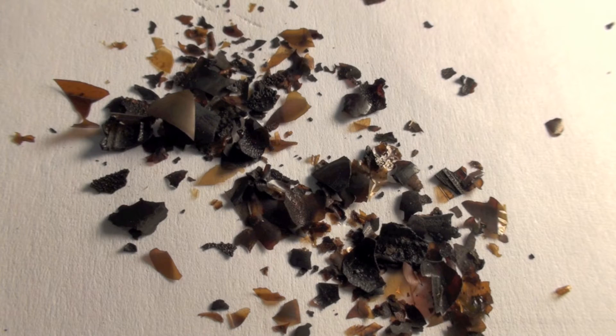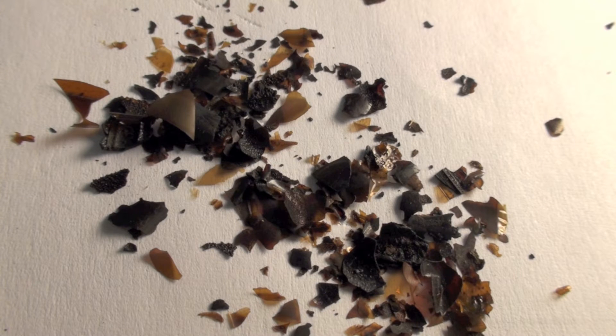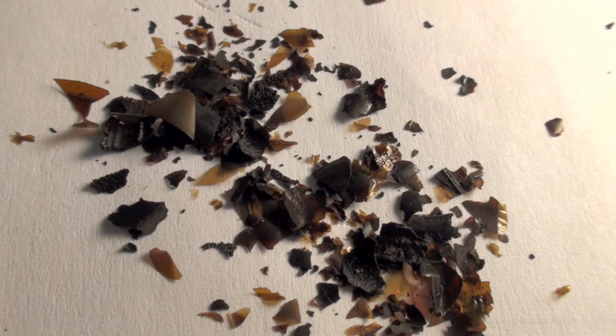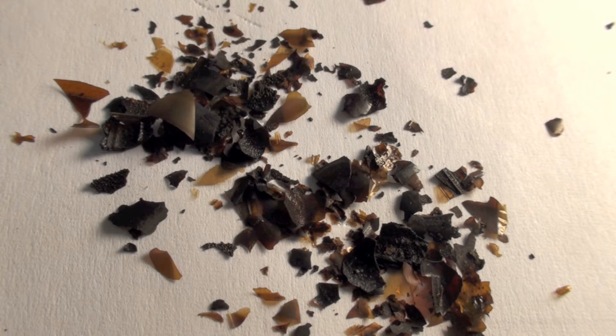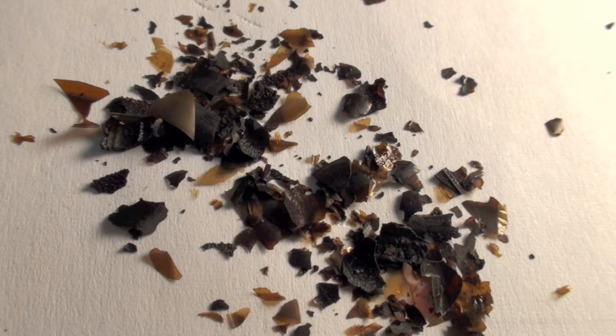This is the lacquer off of the windings of the motor in the motor compressor assembly. This unit was running as it was burning up.